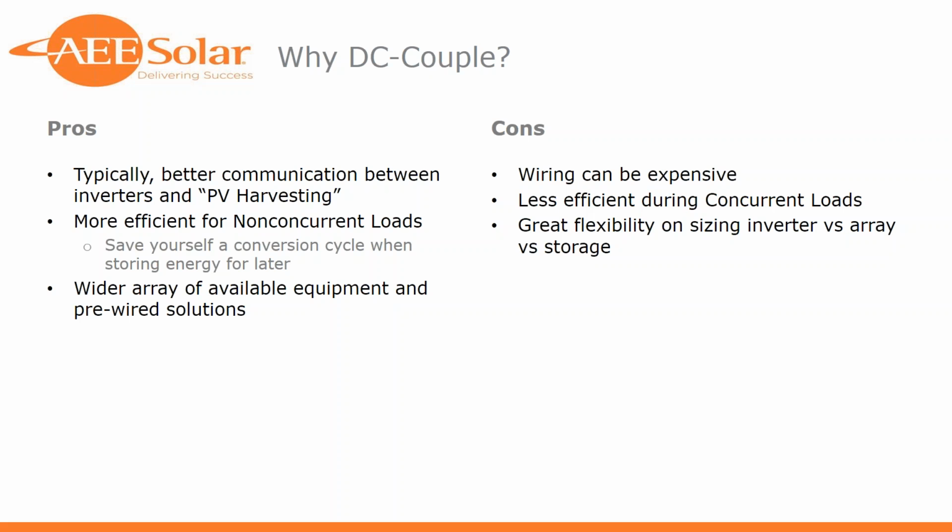So PV harvesting, that's kind of a nonsensical term. Josh, you made that up. Yeah, to compare apples to oranges here, I use the term PV harvesting so that we can compare a charge controller versus a PV inverter. So when I say better communication, in most instances on the DC coupled solar plus storage system, you're going to be running material of similar brands that can speak to each other through FlexNet, through Xanbus, through kind of proprietary communication, and your inverter and your charge controller will work in harmony to make sure you're harvesting the right amount of power based on what your batteries and what your loads need to see.